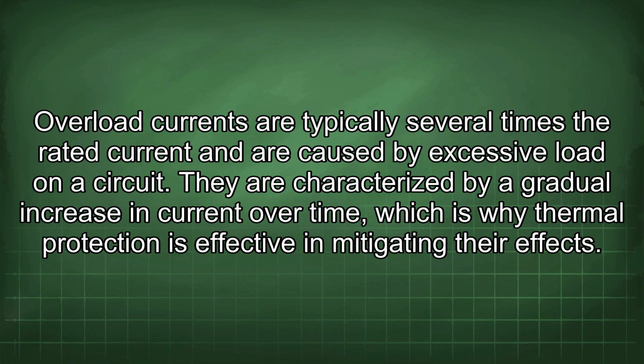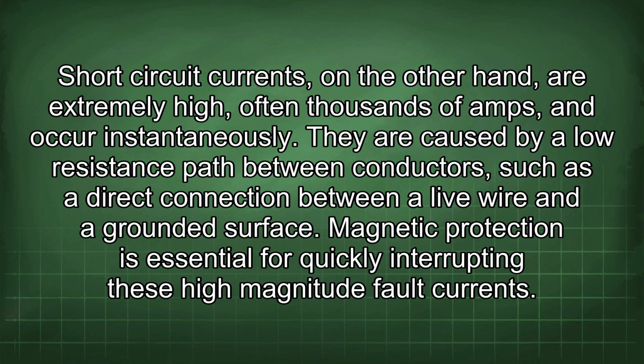Short-circuit currents, on the other hand, are extremely high, often thousands of amps, and occur instantaneously. They are caused by a low resistance path between conductors, such as a direct connection between a live wire and a grounded surface. Magnetic protection is essential for quickly interrupting these high-magnitude fault currents.